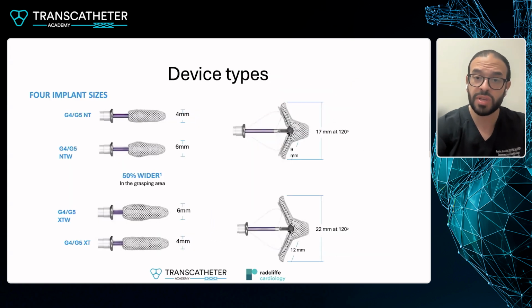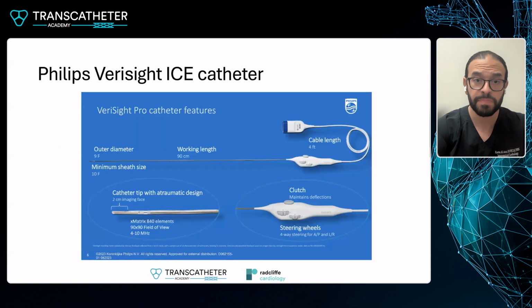These are the device types that are provided in general. Typically, what we use is the XT and XTW devices. The XTW device width is 6 millimeters with a length of the clip arms of about 12 millimeters, and the whole device expands to about 22 millimeters at 120 degrees. This is typically what is used and is considered the workhorse for a lot of these transcatheter tricuspid edge-to-edge repair procedures using the TriClip system.